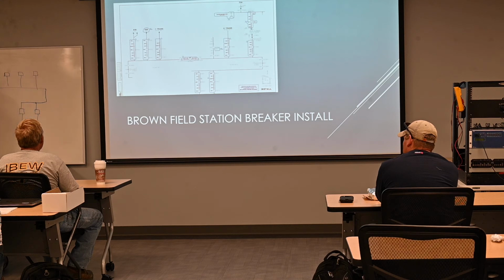All right, so number one, this station has bus differential protection. Most stations will. Like a 480 volt switchgear, distribution switchgear may not, probably doesn't have it, but anything 4 kV, 11 kV, most all of it will have some kind of bus differential protection. And so when I say bus differential protection, does everybody know what that means?